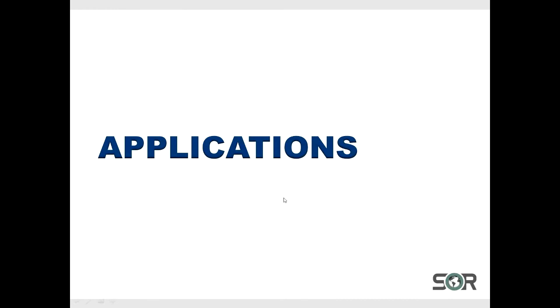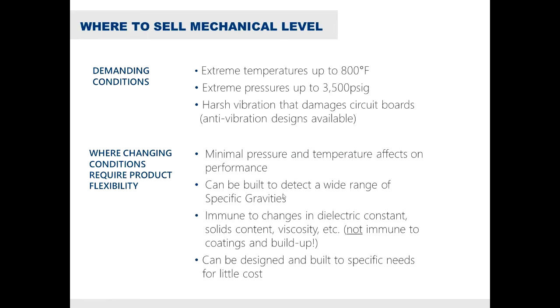Moving on to applications — where to sell mechanical levels. Mechanical level is a proven technology that's been on the market for 80-plus years and is not going away. It has a marketplace where it's one of the best options for certain applications. Some of those areas are demanding applications: over 800 degrees Fahrenheit, pressures upwards of 3,500 PSI, and harsh vibration applications — there are really not many other technologies that can handle these extreme process conditions.